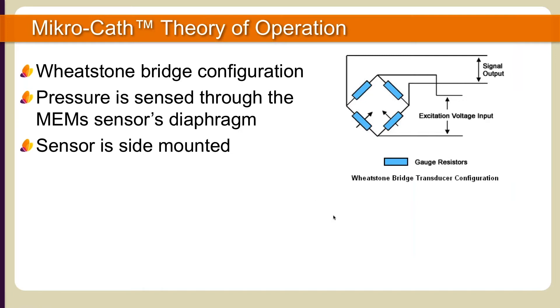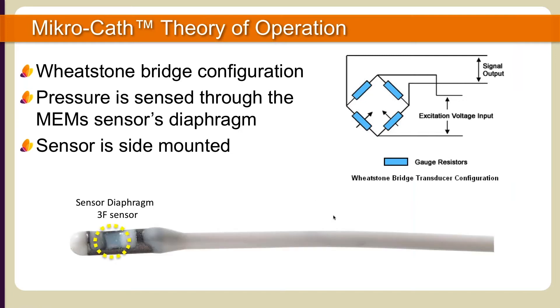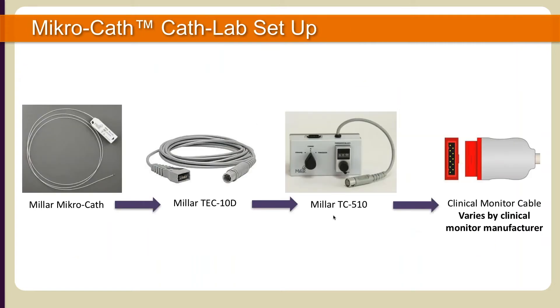The Microcath is designed using a Wheatstone bridge configuration containing a pressure-sensitive membrane known as a sensor diaphragm. The diaphragm is side-mounted on the distal sensor case. The sensor measures the summation of the mechanical pressure that impinges on the diaphragm and converts that to a voltage signal, which can be calibrated to a known value of millimeters of mercury.